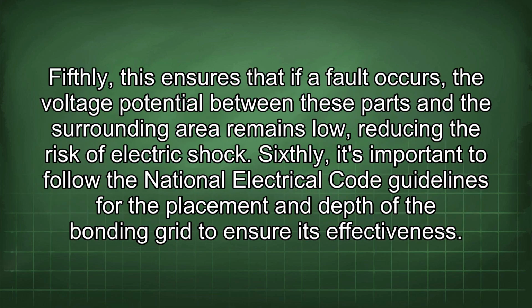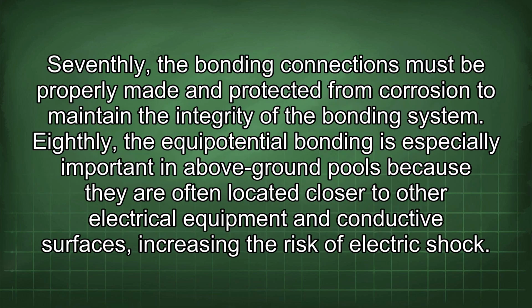Fifthly, this ensures that if a fault occurs, the voltage potential between these parts and the surrounding area remains low, reducing the risk of electric shock. Sixthly, it's important to follow the National Electrical Code guidelines for the placement and depth of the bonding grid to ensure its effectiveness. Seventhly, the bonding connections must be properly made and protected from corrosion to maintain the integrity of the bonding system.